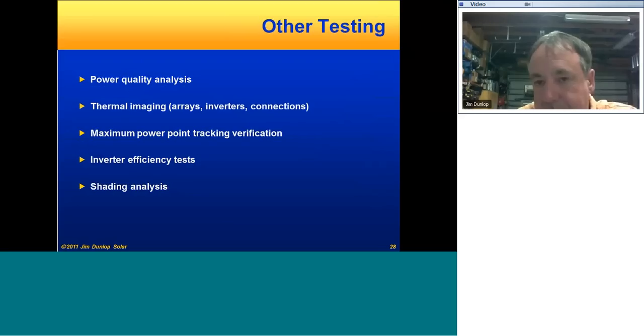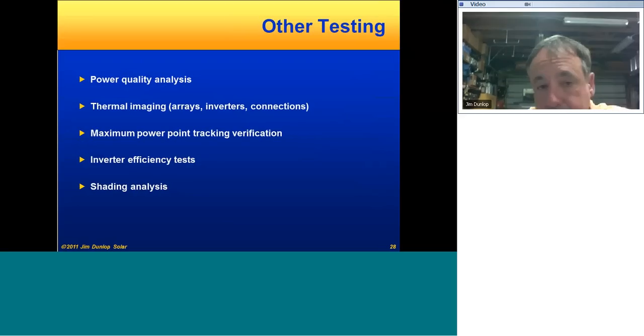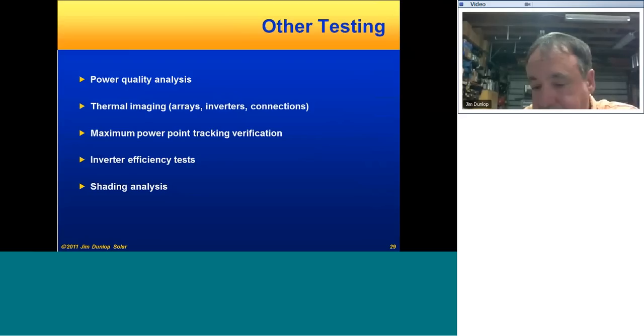A lot of other tests might be done as well. Power quality analysis, looking at interconnection issues, maybe inverters are dropping offline. You've got to look and see what the problems are. You have to look at the AC signal and see what's going on there. A lot of guys are doing thermal imaging on arrays. Obviously, inverter cooling, any wiring connections, terminations, junction boxes, combiner boxes, you can easily detect problems that you wouldn't be able to tell visually. You can do inverter efficiency tests, shading analysis, which obviously we all know about.